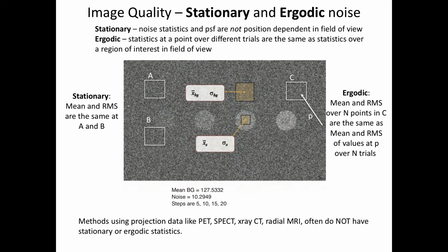That's stationary, okay? And so that means if I'm, say, doing a very simple evaluation of signal to noise, I can pick a background anywhere, measure my root mean square deviation of the background anywhere, and then look at my signal. So in this image, it's not a big deal, but in a clinical image, sometimes there's just a little bit of air in the background. And you want to measure the noise there because everywhere else has signal corrupting your noise measurement, right? So all of your deviation and measurement would be from the actual signal or the picture. And then over in the corner, you have a little bit of air and it's uniform. And so you can put an ROI there and measure the standard deviation of the noise, right?